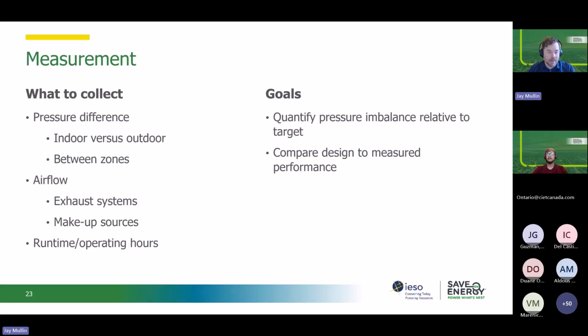The next part of this then is measurement. So where you're wanting to collect pressure difference, getting some data on what is the pressure difference between inside the facility, outside the facility, but also between zones. Because if there's an office area, production facility, paint area, warehouse, there may be separations between zones in your facility, and getting actual data around what are the pressure differentials there can help zero in on what are the issues.